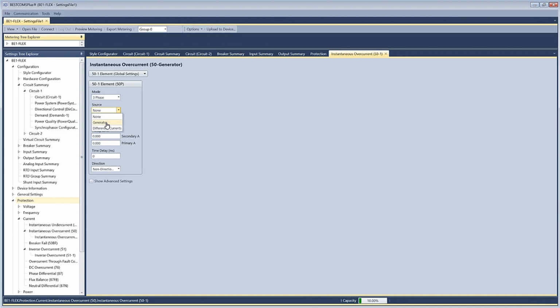I give it a source. So remember, if up in the circuits I had named it generator or differential currents, I want to use and look at my generator source, so that's the current inputs, and then what pickup level do I want it to pick up at, and do I want to add an intentional time delay? And I'm going to say 0, and in this particular case, that's going to make the 50 element pickup go true at the same time as the 50 element trip.